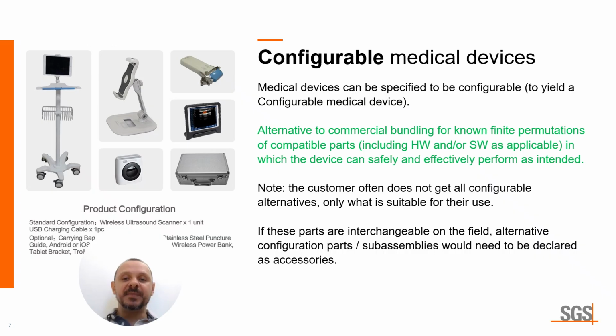Medical devices can be specified to be configurable, to yield a configurable medical device. And so this is an alternative to commercial bundling for known finite permutations of compatible parts, including hardware and software as applicable, in which case the device can be safely and effectively performed as intended. The customer often does not get all the configurable alternatives, only what is suitable for their use.